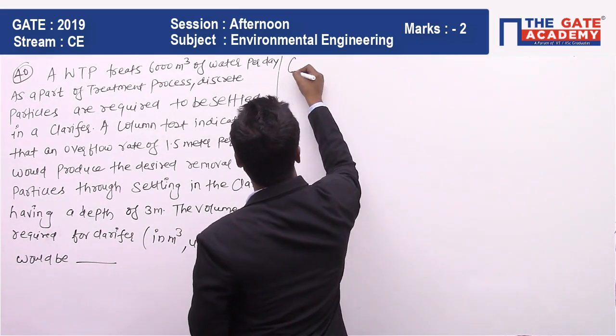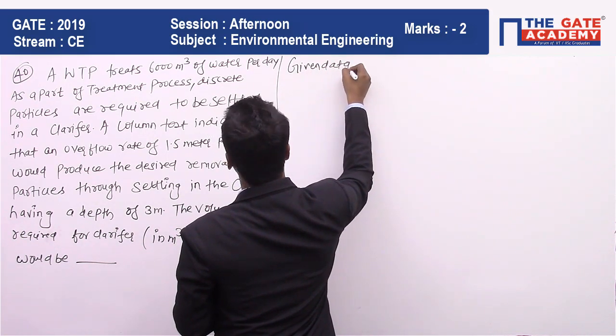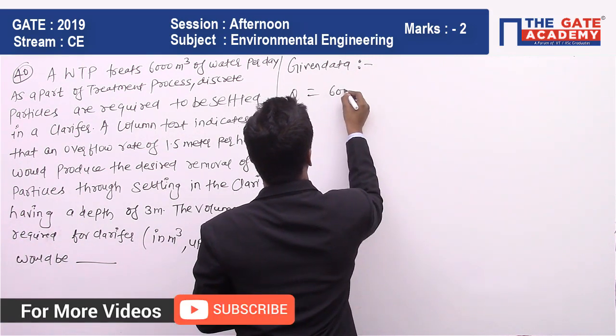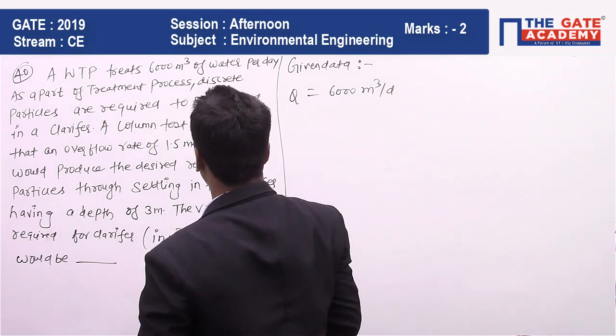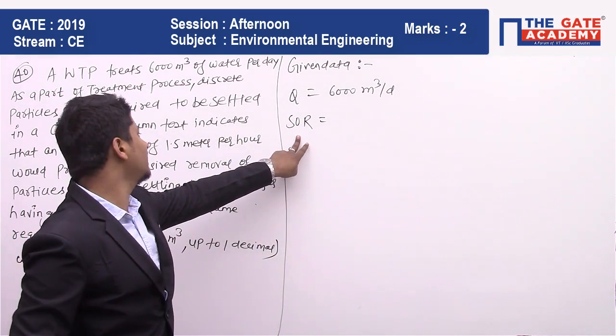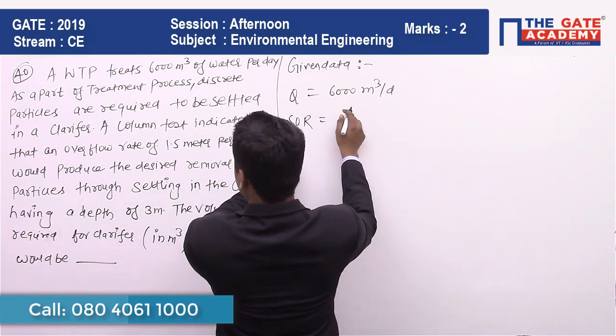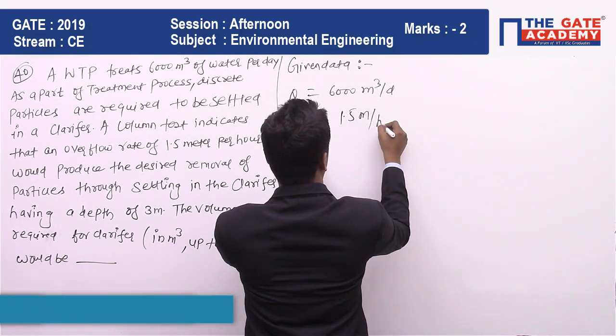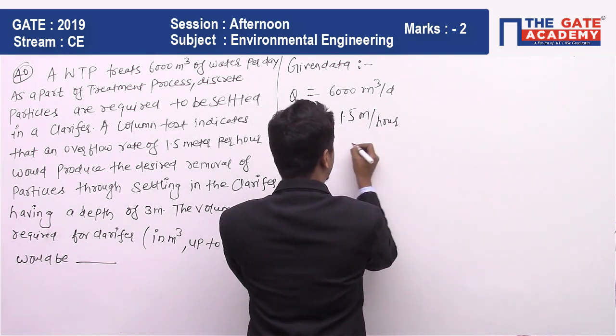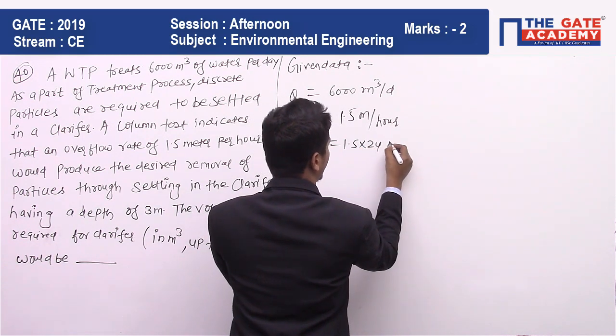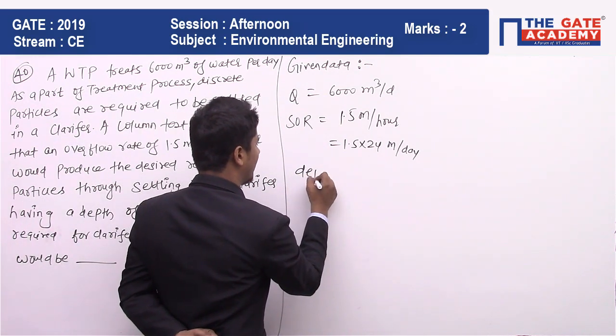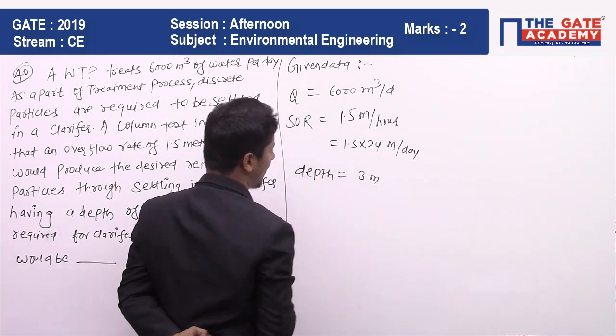So what are the given data? We have Q = 6000 meter cube per day. We have the surface overflow rate, SOR = 1.5 meter per hour. Since Q is in per day and SOR is in per hour, I am converting SOR as 1.5 × 24 meter per day. Next, the depth of the clarifier is given as 3 meters, and they are asking for the volume.